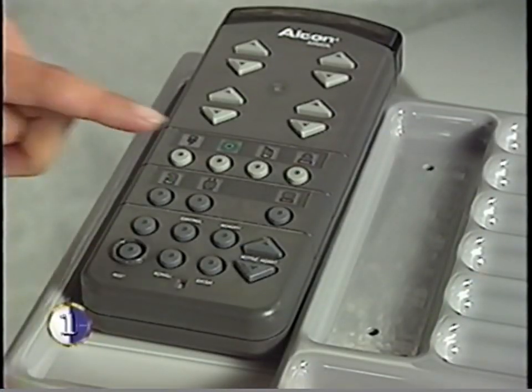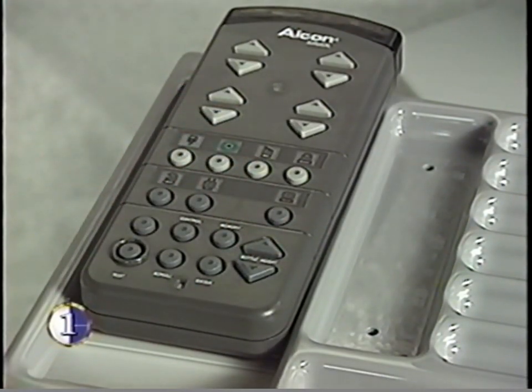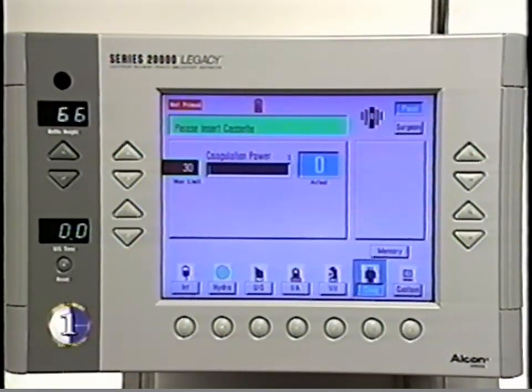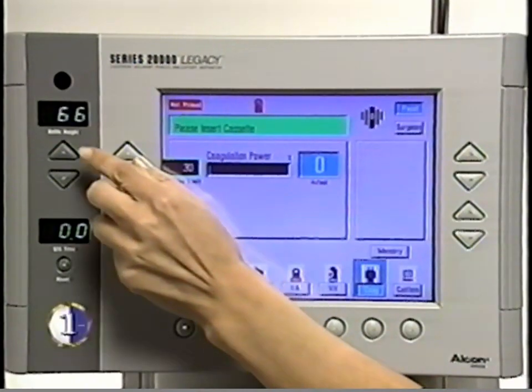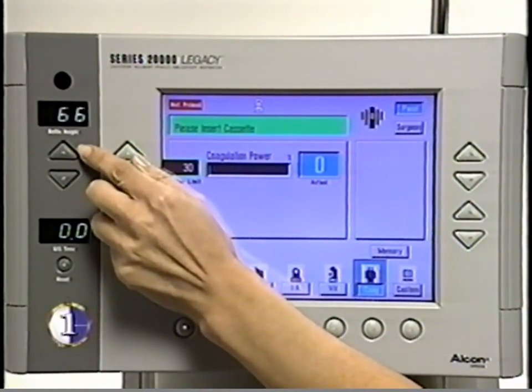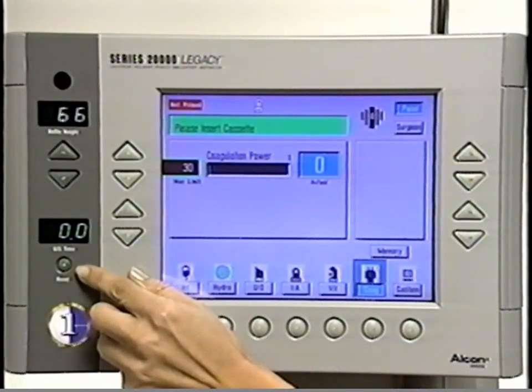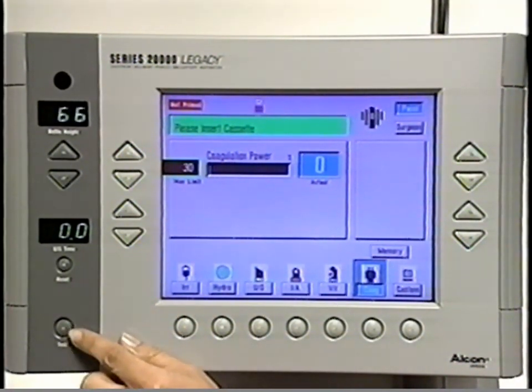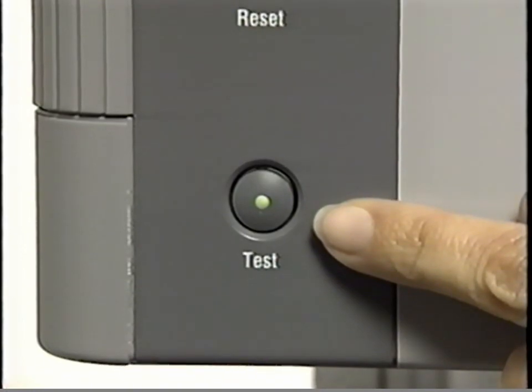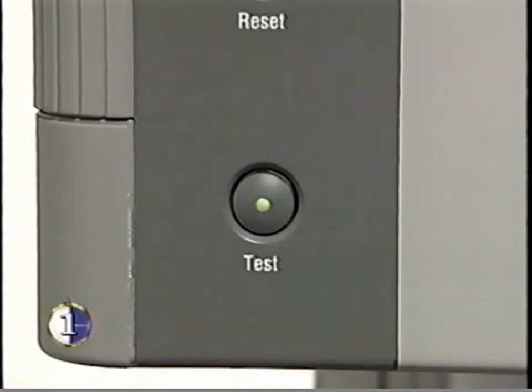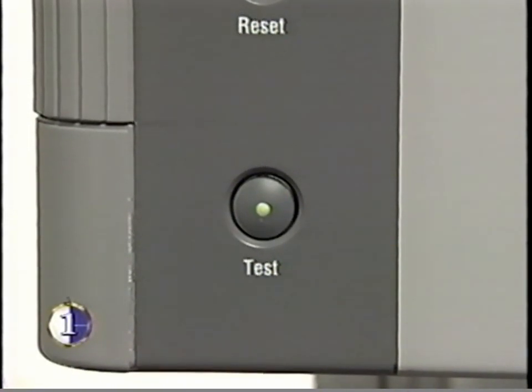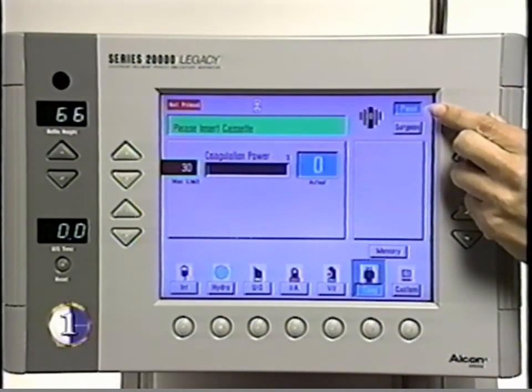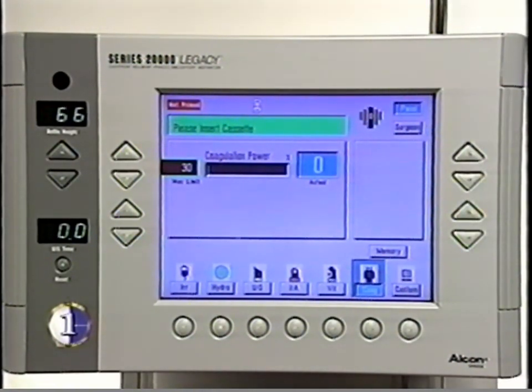You can also select operating modes using the remote control. Other buttons and display screens on the control panel are used for adjusting and displaying the height of the irrigation bottle, monitoring and resetting elapsed time during ultrasound use, system testing, system priming, and automated system teardown, and determining control of aspiration flow rate, vacuum limits, and ultrasound power between the control panel or the foot switch.